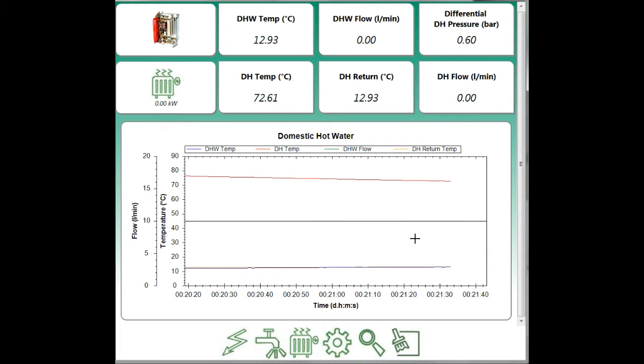Domestic hot water temperature in blue shown at about 12.9 degrees at the moment. This is because we've run some cold water through the HIU before the test. The district heating temperature is about 72 degrees C. This is in red.